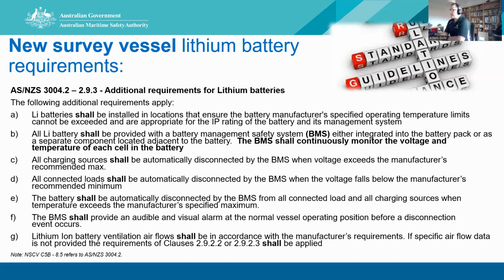Lithium-ion battery ventilation airflow shall be in accordance with the manufacturer's requirements, and if there's none, it's got to be in accordance with the standard 2.9.22 and 2.9.23, and they are a shall. I'll take questions at the end anyway. My audio, I can't hear anyone, so that means there's no questions coming in, so that's good.